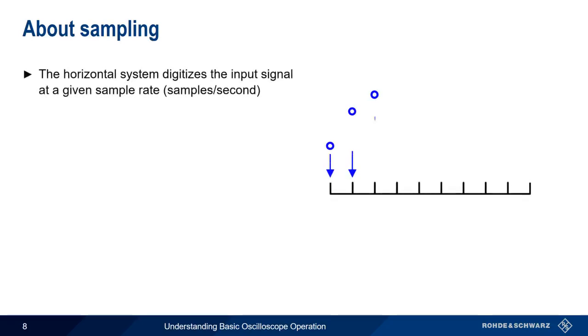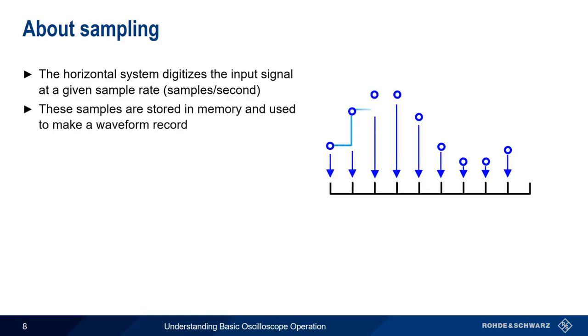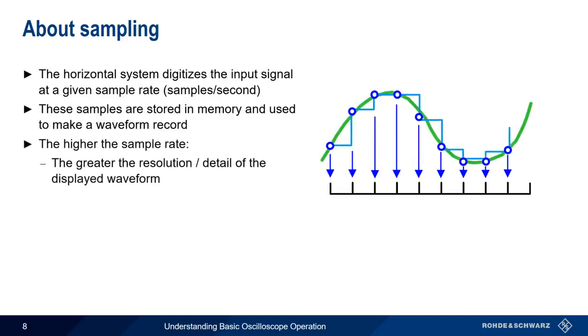The more important aspect of the horizontal system is something called sampling. The horizontal system digitizes the input signal at a given sample rate, in samples per second, or at every sampling interval. Samples are stored in memory, and together these make up a so-called waveform record. As we increase the sample rate, we get better resolution and more detail of the displayed waveform. And this in turn increases the probability that we'll see or catch infrequent events.